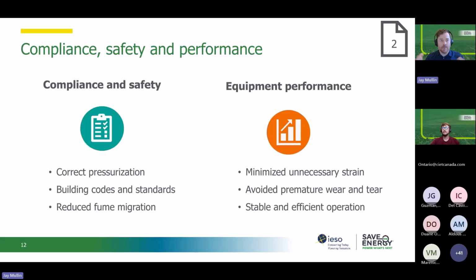So, for a paint booth, if you have an opening in your paint booth, you need to keep a capture velocity of the airflow across that opening for safety reasons so fumes don't escape into the area where there are people. If you have negative pressure in your facility, it could impact the effectiveness of that, reduce the capture velocity, and allow some of those fumes to escape. So there are lots of benefits around safety, and also equipment performance. As I mentioned, adding unnecessary static pressure to this equipment can cause issues with maintenance and strain on fans. Having this balance can help extend equipment life, prevent premature failure, all those good things.